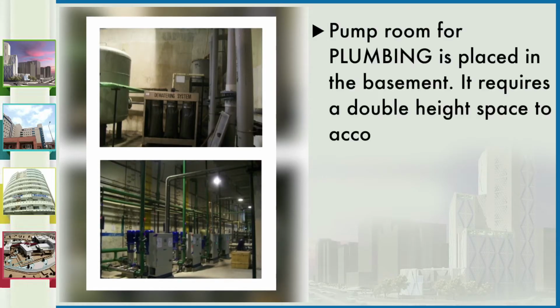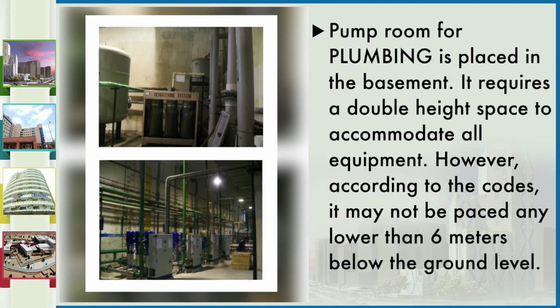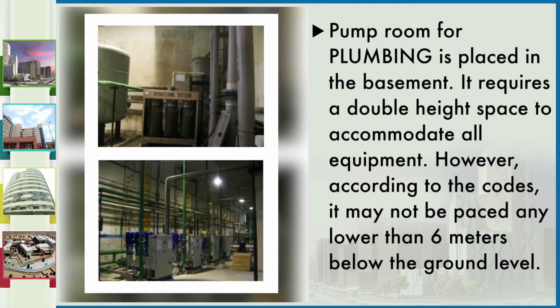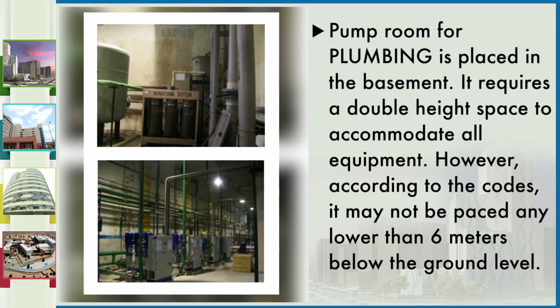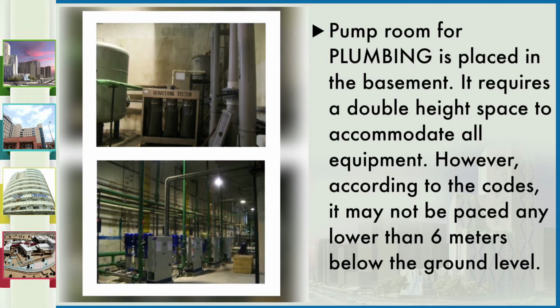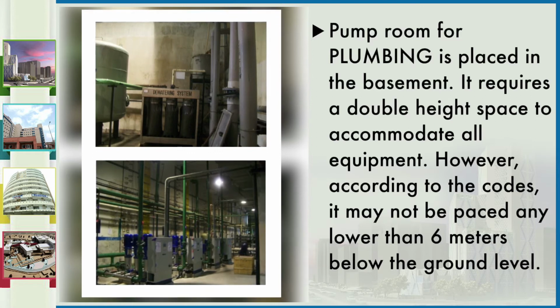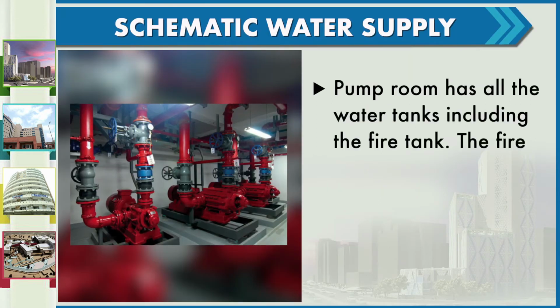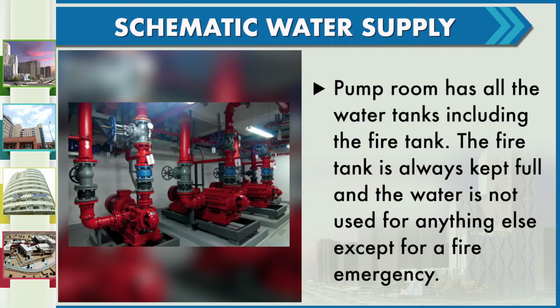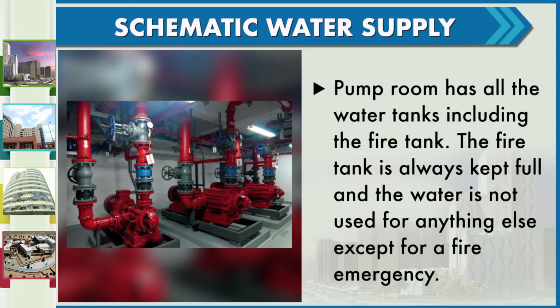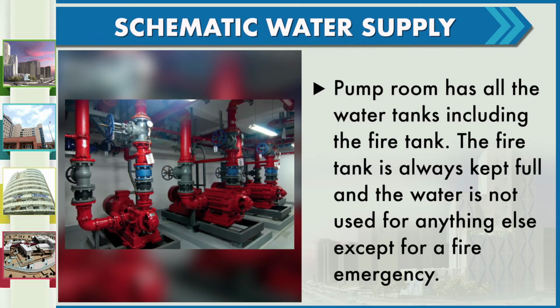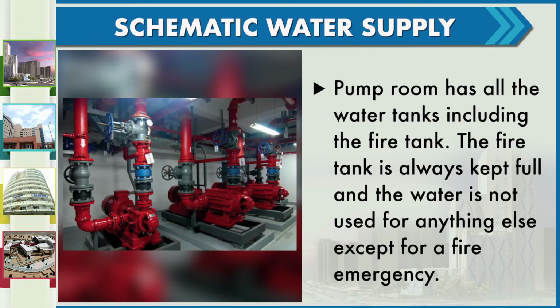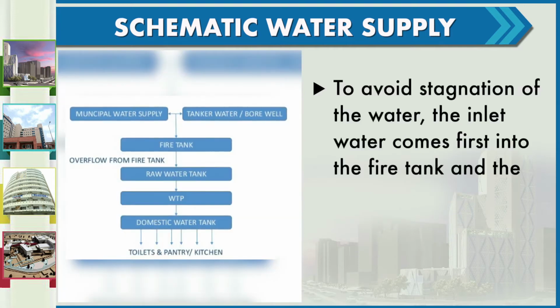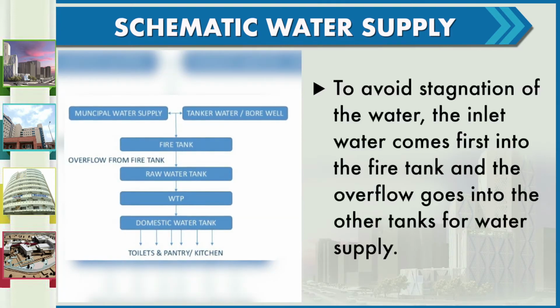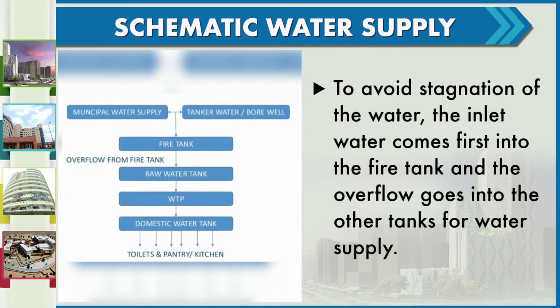Pump room for plumbing is placed in the basement. It requires a double height to accommodate all the equipment that is there. However, according to the codes, it may not be placed any lower than 6 meters below the ground level. Pump room has all the water tanks, including the fire tank. The fire tank is always kept full and the water is not used for anything else except for a fire emergency. To avoid stagnation of this water, the inlet water comes first into the fire tank and then the overflow goes into the other tank for water supply.